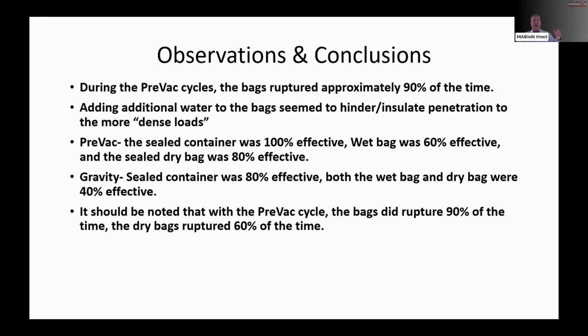In order for everything to work, you need your contents to be susceptible to that steam and pressure. Plastic bags are an insulator. Water is an insulator. So if you use the bags and you seal them up and you use the water, you're causing it to get to sterilization slower. My guess is that when it gets into sterilization, that water gets to temperature and you get that sudden drop, boom, there goes the bag, because now everything's getting hot and it explodes and now your bag's blown up, but now you're not getting it.